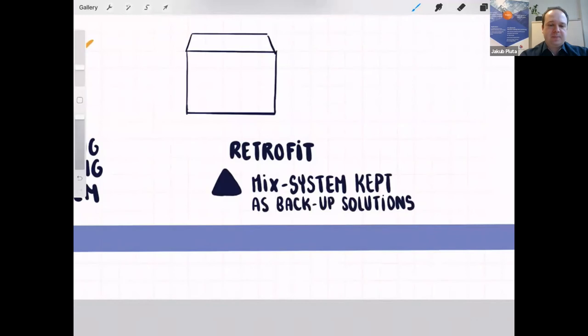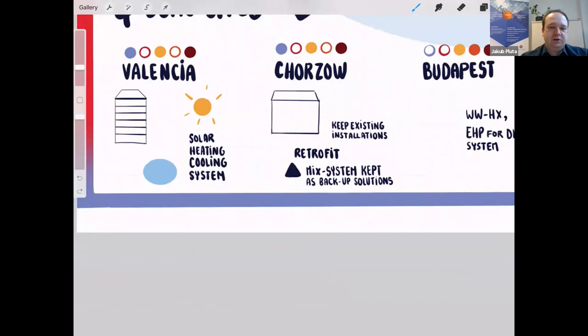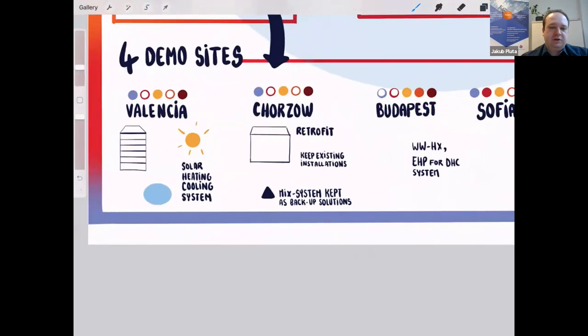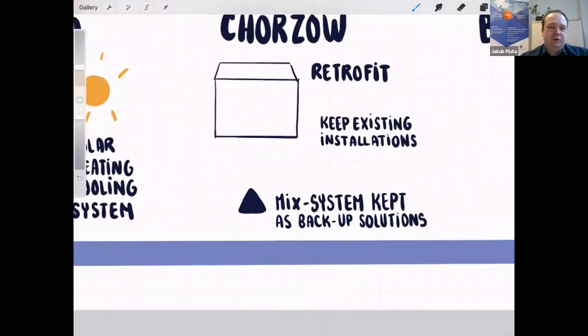Regarding the second question, as I shortly presented in the presentation, the modernization regarding the independent work of the gas boiler and the circulation pump is due to this: we wanted to minimize as much as possible the gas consumption by the boilers. So the circulation pump is running the water in the apartment, taking the heat from the heat pump circuit through the heat exchanger. But only if the heat provided from the heat pump is not enough, then the boiler will start the gas burner, causing the gas consumption. So we wanted to, as much as possible, maximize the use of the heat pump and minimize the gas consumption. Okay, thank you.